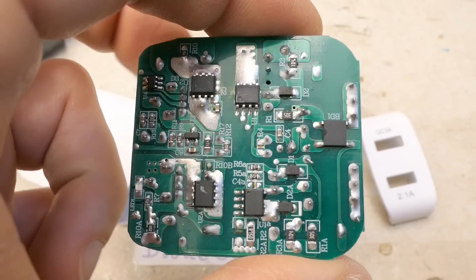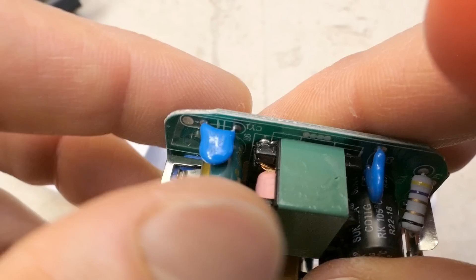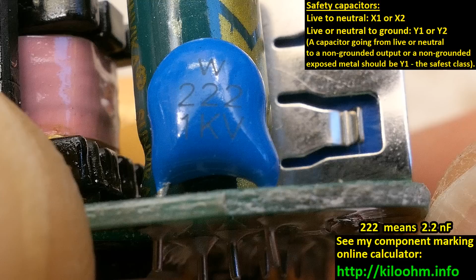The isolation is here. It's sort of kind of there, even though it could be better - there is some capacitor between the primary and secondary side. Is it a safety capacitor? Of course not - it's just an ordinary 2.2 nanofarad 1 kilovolt capacitor, but in this position between the primary and secondary side it should be a safety class Y1 capacitor, because it's the only thing isolating the user from mains.